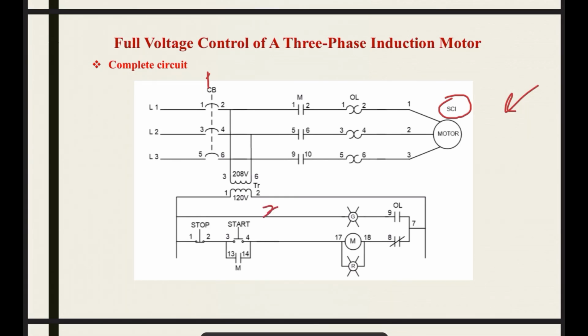Second, depress the start push button. Third, the M contactor energizes. This is the main coil M, and it energizes. So the M normally open contacts in the control circuit close for holding. Also the M normally open contacts in the power circuit close. Then the motor starts running, the motor now runs.